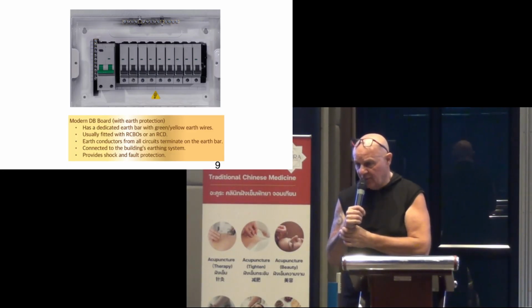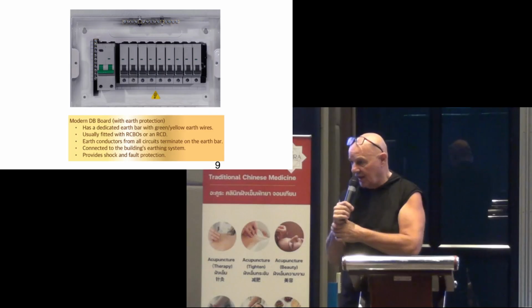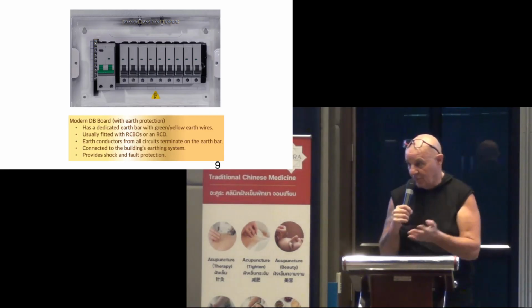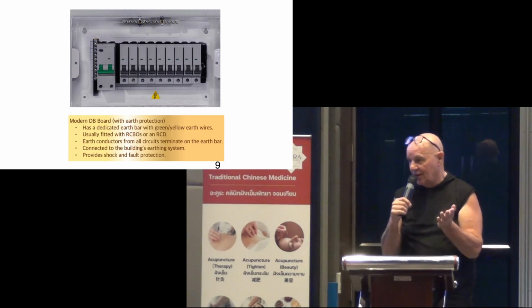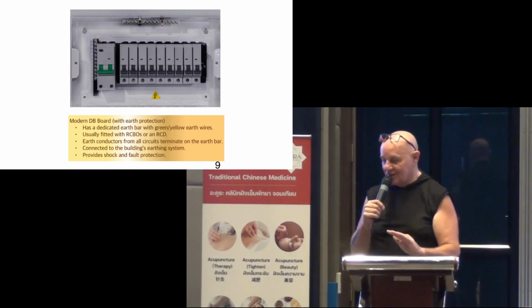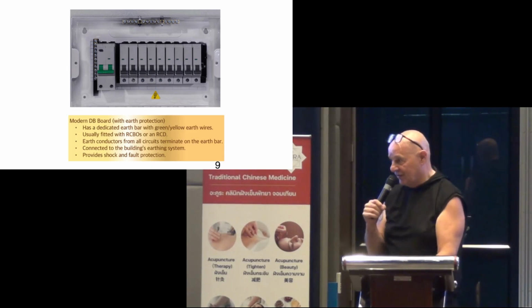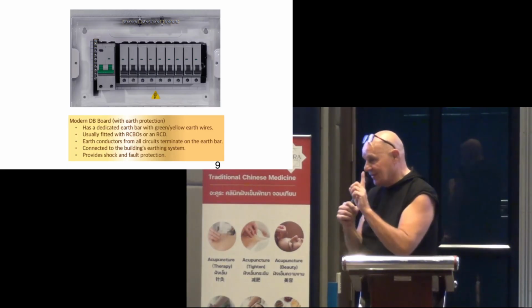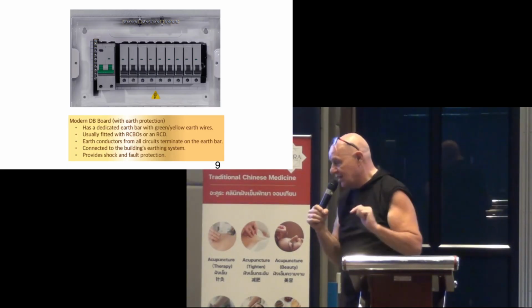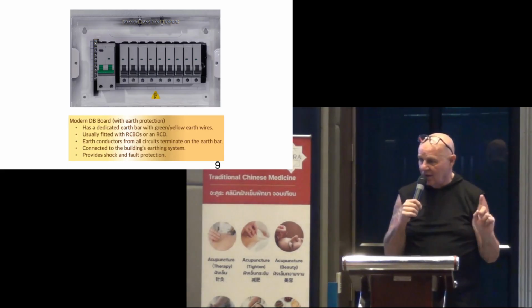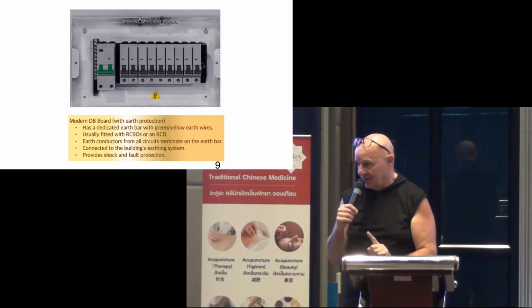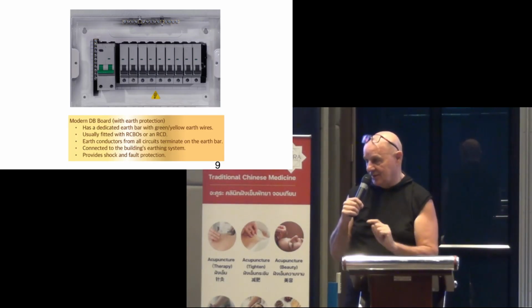But there are some condos out there that don't have it yet - the older ones don't even have it. Whether they're going to get it, I don't know. So in that instance, if you know you don't have an earth system, the safest thing is to put in one of those RCBO devices. It will give you protection. They'll work even without a building-based ground system - you don't have to have ground for that to work.